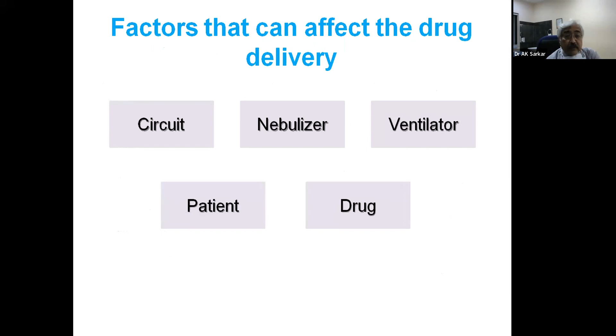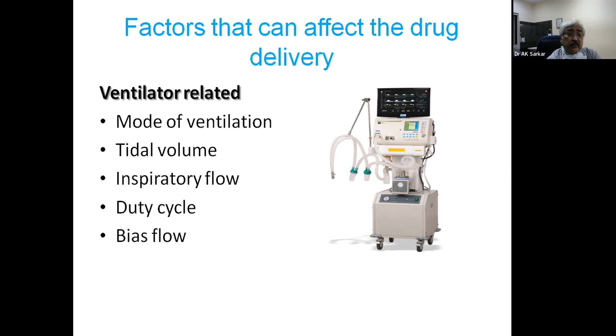The mode of ventilation has to be chosen. The tidal volume has to be set. The inspiratory flow, how much inspiratory flow we should give, is important. Duty cycle, that means the inspiratory fraction of the total cycle, also has some effect. I'll come to that. And the bias flow, a slow flow, will always affect the drug deposition. Bias flow in high flow oxygenation is very high, so that machine cannot be used for nebulization. So regarding ventilator related factors, we will come to those points.